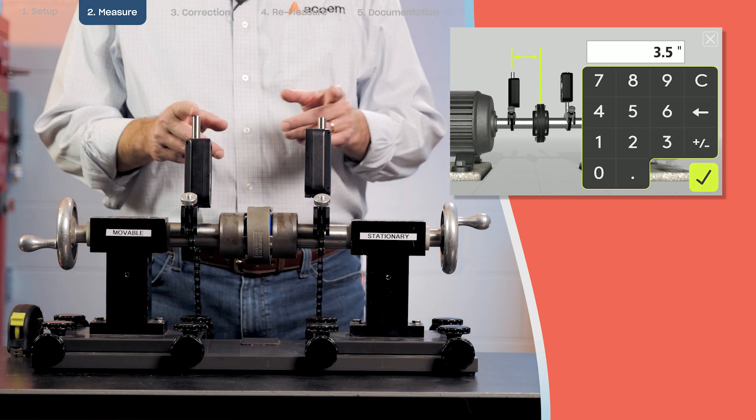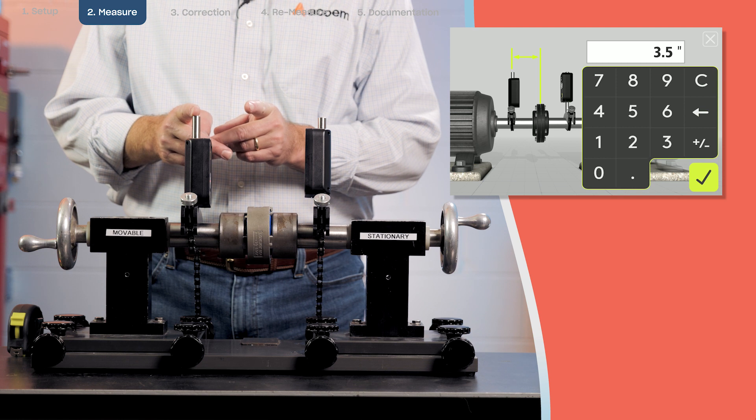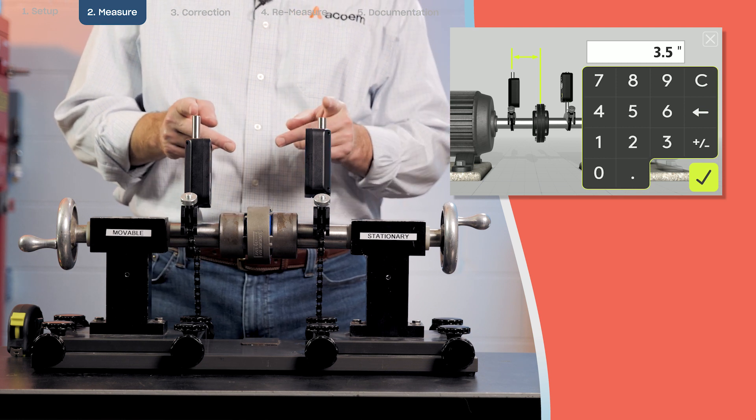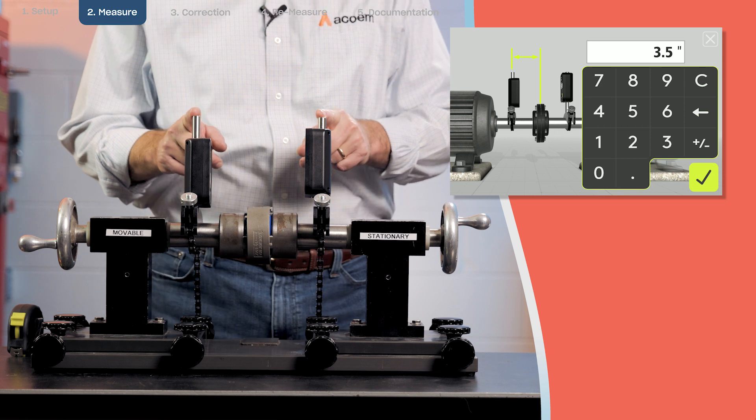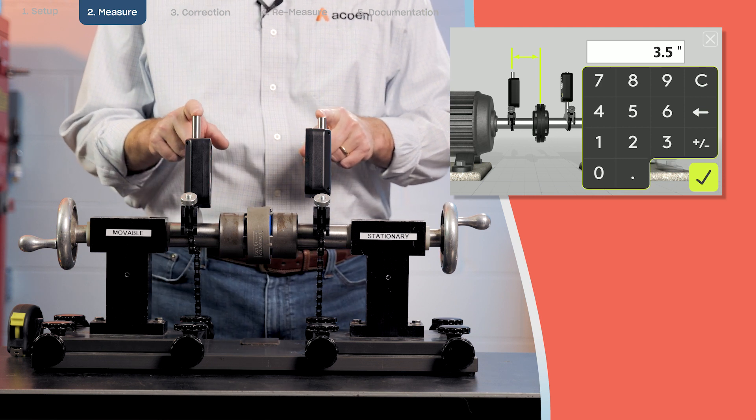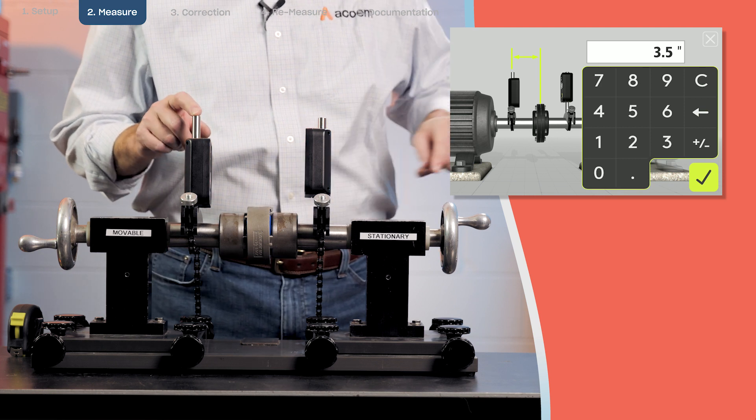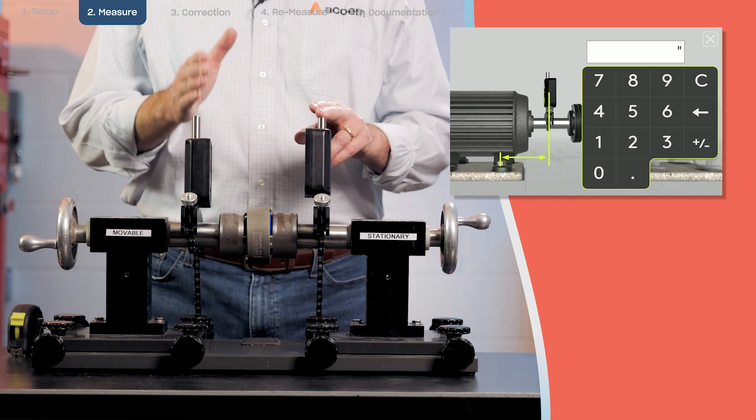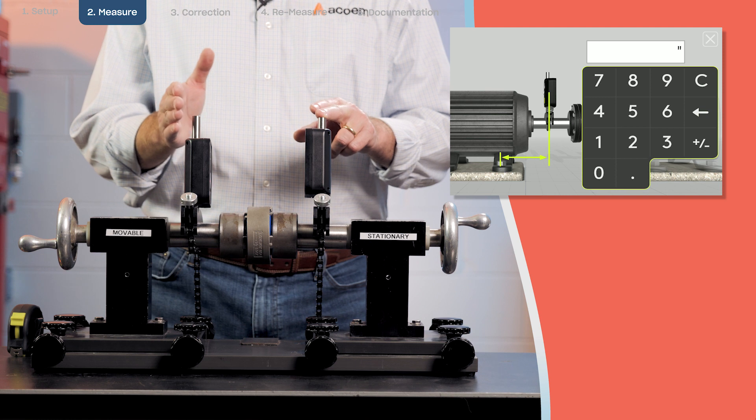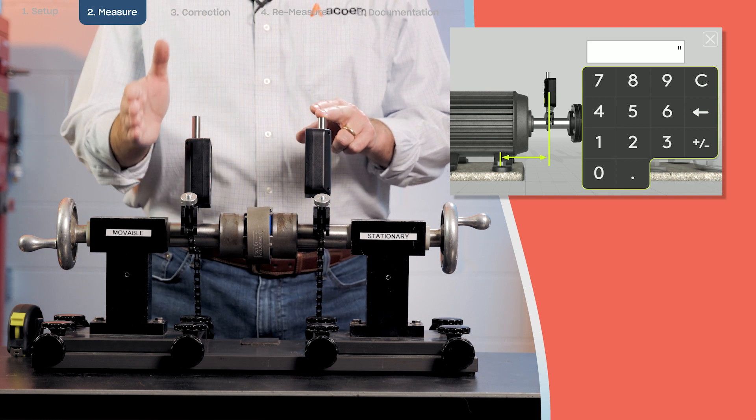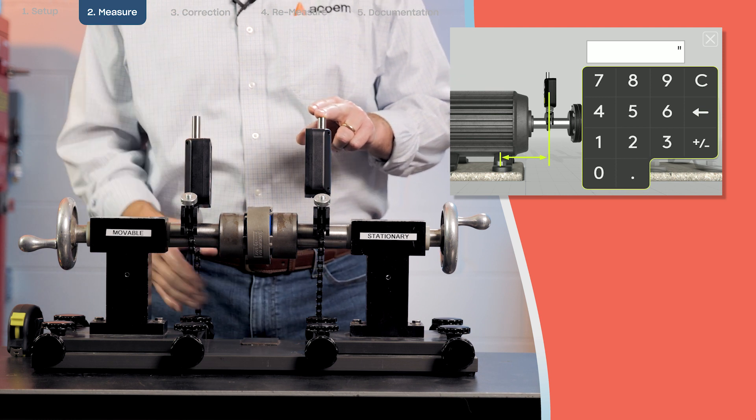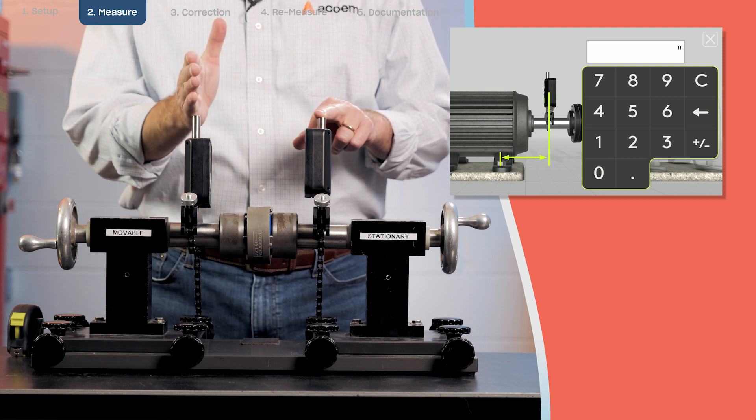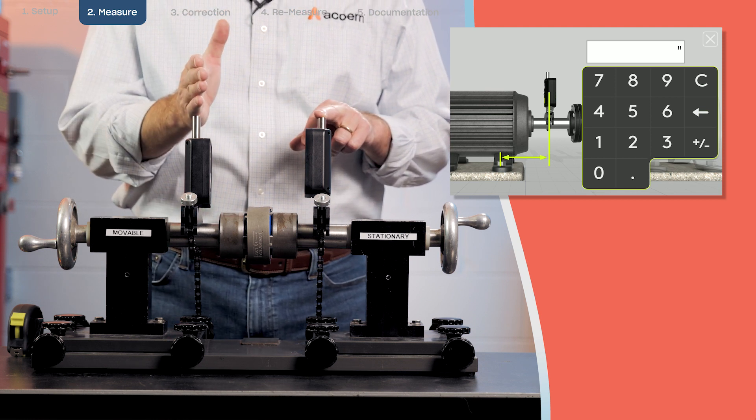The next dimension is from M sensor to the center of the coupling. In this case I have the default value of half the distance between the S sensor and M sensor. If it's not, you can change that to what the actual measurement is. Then we have from M sensor to the front feet of the movable machine or the motor. In this case you can see if I use my chain as a plumb bob that my M sensor is straight over top of my motor feet.